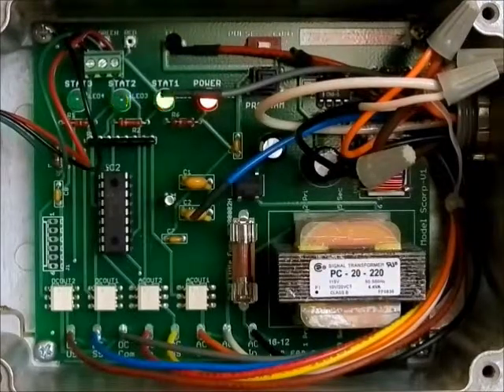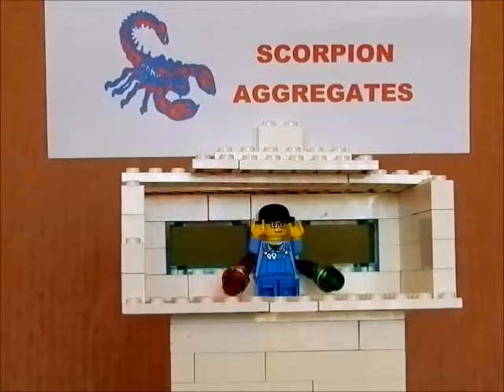STAT1 indicates the presence of the Scorpion target and flashes as the target moves in and out of range. STAT2 shows the status on the speed switch output and will flash at the same rate as STAT1 when the SC1 is set to pulse mode. Similarly, we will see that Mr. B has a flashing speed switch indicator in his control tower.